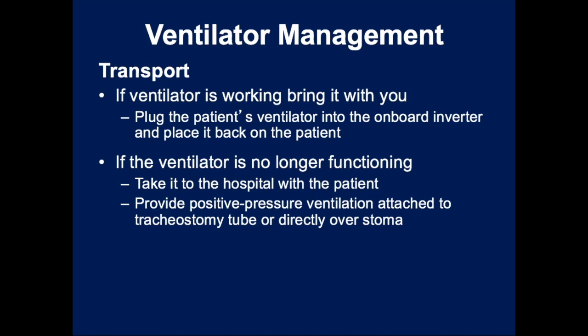So for these patients, if you find out the ventilator is working just fine, you can go ahead and put them back on that ventilator or keep them on the ventilator and bring the vent, if it's portable, with them to the hospital. If it's not functioning, then go ahead and manually ventilate that patient, like I said, and then bring the ventilator with them to the hospital if possible, and they can help troubleshoot it at the hospital.